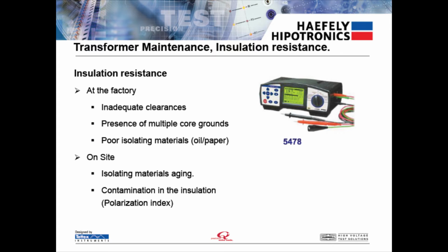So measuring transformer maintenance limits for insulation resistance. This is using our 5478 tera ohm meters. You use it at the factory on site as well.